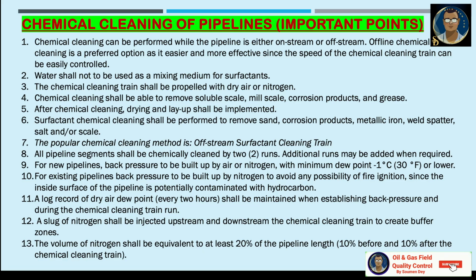Surfactant chemical cleaning shall be performed to remove sand, corrosion products, metallic iron, weld spatter, salt or scale. The popular chemical cleaning method is the off-stream surfactant cleaning train. All pipeline segments shall be chemically cleaned by 2 runs. Additional runs may be added when required. For a new pipeline, back pressure to be built by air or nitrogen with a minimum dew point of -1 degree centigrade or 30 degree Fahrenheit or lower.